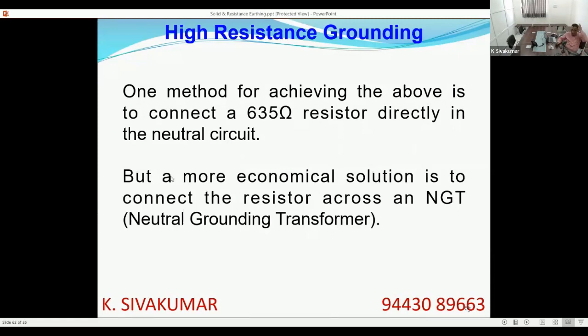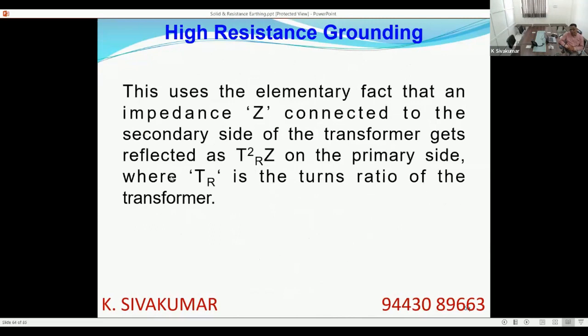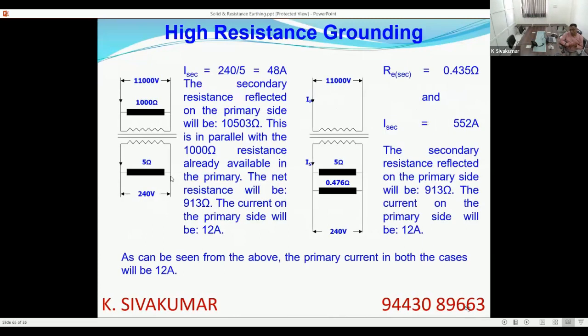But if you use a small transformer, an NGT, neutral grounding transformer, and provide a very small resistance in the secondary of the neutral grounding transformer, that will reflect as a very high resistance in the primary of the transformer. This is the basic transformation theory. It uses the elementary fact that an impedance connected to the secondary side or LV side of the transformer gets reflected on the high voltage side as the impedance multiplied by the square of the turns ratio, where TR is the turns ratio.